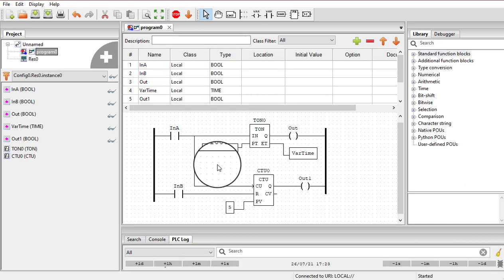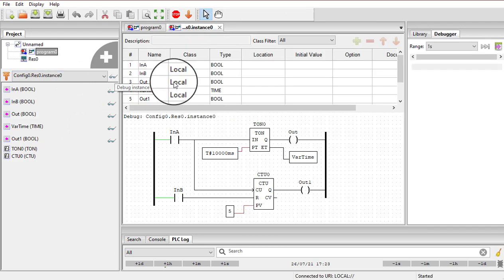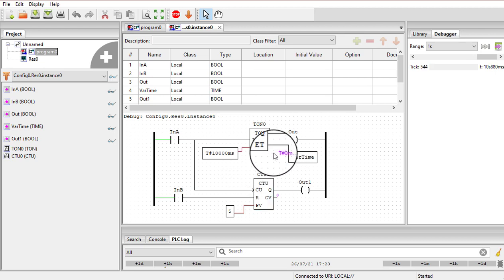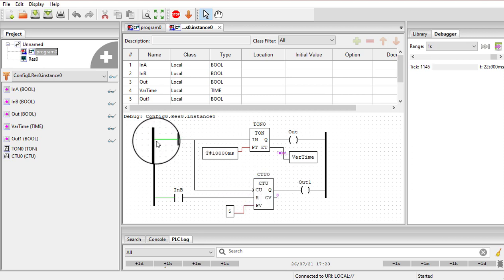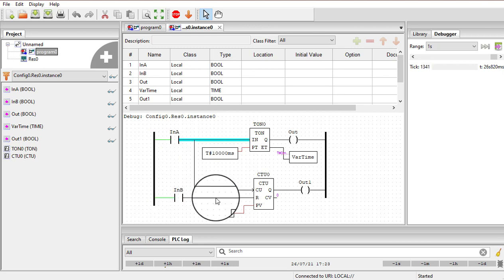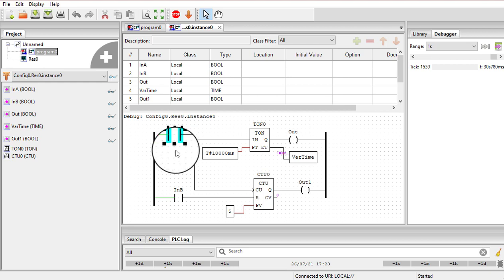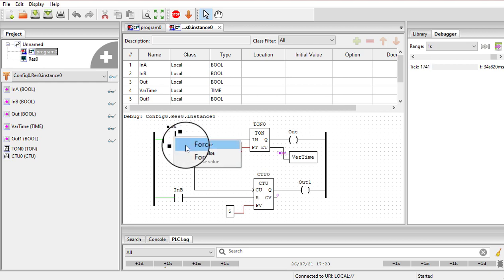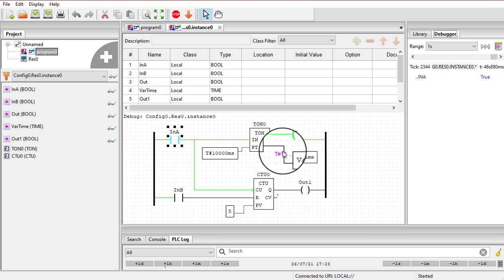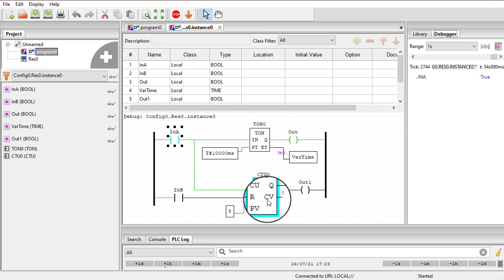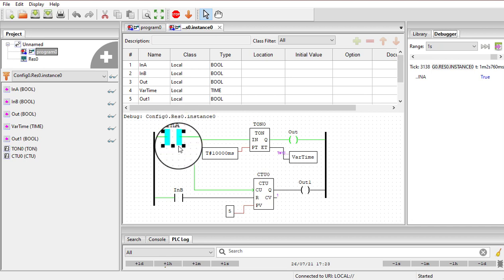Let me run this PLC. The PLC is running and I am going into the debug instance. Right now the elapsed time is t#0 — zero milliseconds — and the counter's current value is also 0. If I right-click on input A and force true, you can see the timer starts timing. It will keep timing until 10 seconds, then the output turns on. The counter's current value is now 1 because input A transitioned from false to true one time.